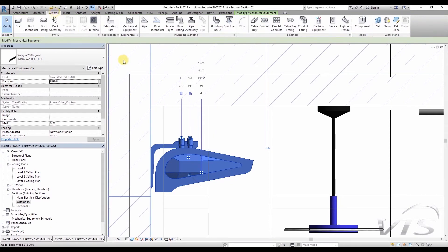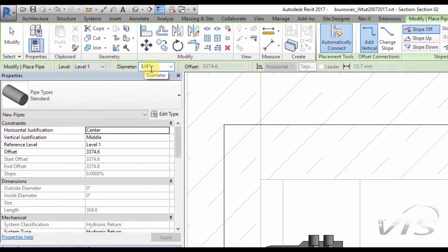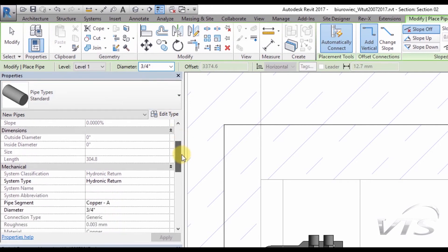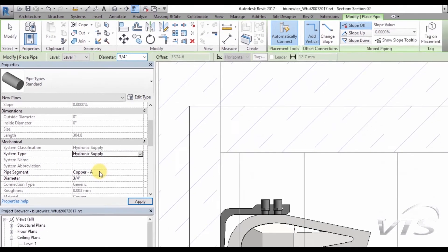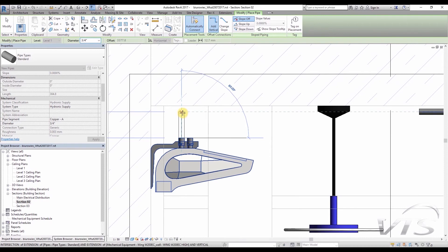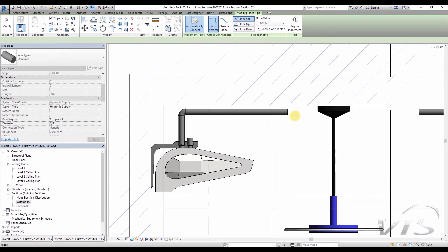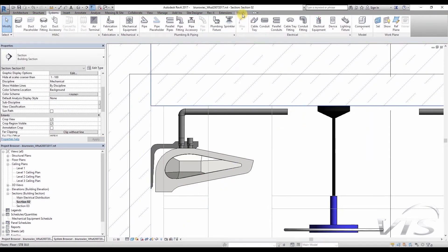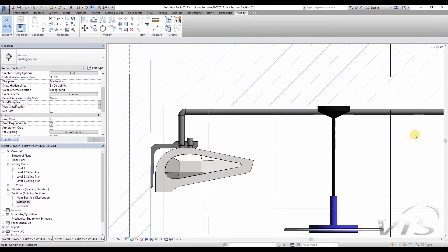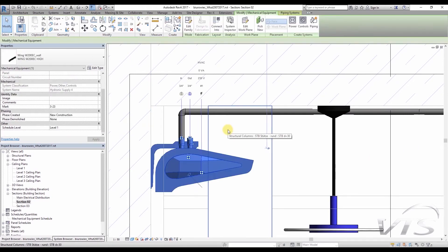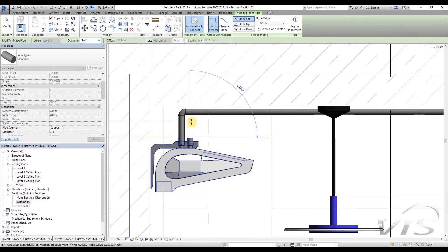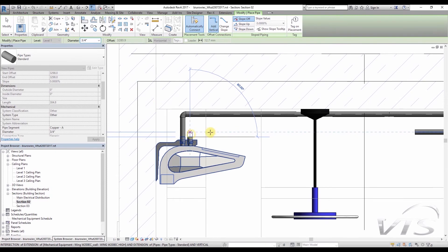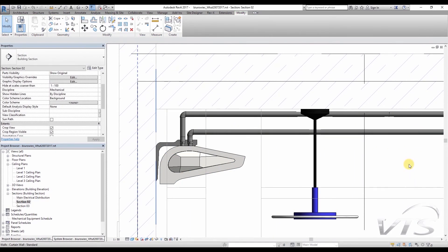In order to connect the curtains to the existing system, I go to the Systems tab, and then I choose the Pipe tool on the ribbon. I make sure on the Options bar that the selected option is 3/4 of an inch, and later in the Properties palette, I choose the System type as Hydronic Supply. I go with the cursor to the drawing area, and I click on the location of the hydraulic connector. I take the pipe upwards, and then I turn to the right in order to connect it with the existing system. I will help myself with the Align tool, which shows to which item the pipe and any other element shall be connected. Now, we can see at once that two elements have been connected. I do the same with the second connector, but this time I will use the information assigned to our device, and I will click on the symbol. The software shall automatically select the appropriate pipe diameter in order to connect it to the existing system. Thus, we have connected the device to the existing water supply system.